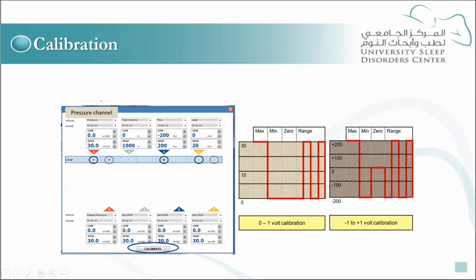Here you have the pressure channel, which goes from 0 centimeters of water up to 20, 30, or whatever. The calibration procedure requires you to calibrate the adequate port, which is between 0 and 1 volt. So 0 volt is equivalent to 0 centimeters of water, and 1 volt is equivalent to 30 centimeters of water.